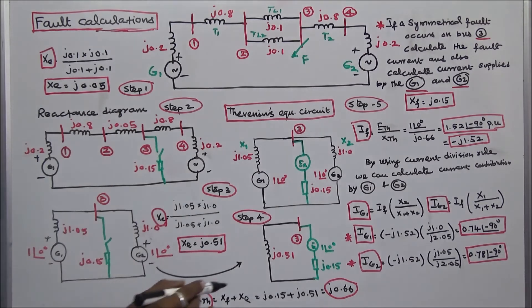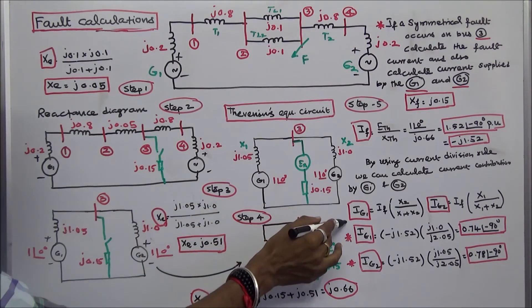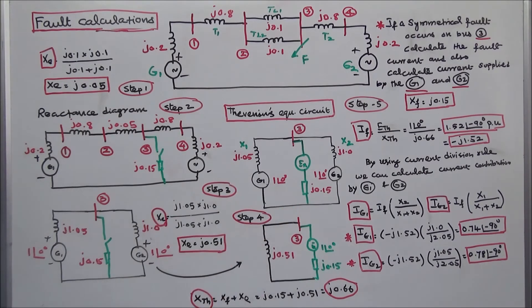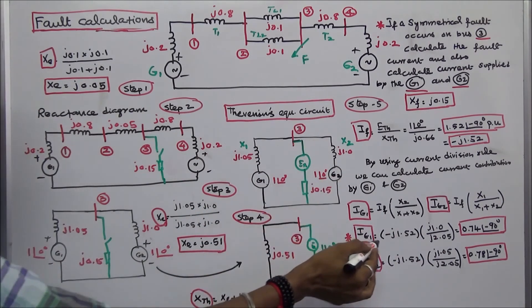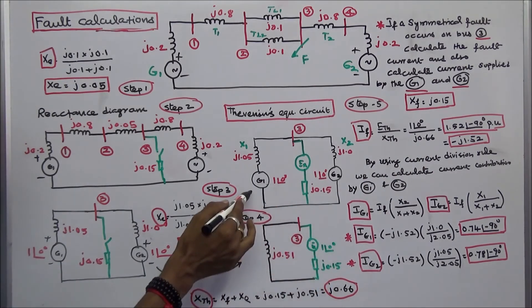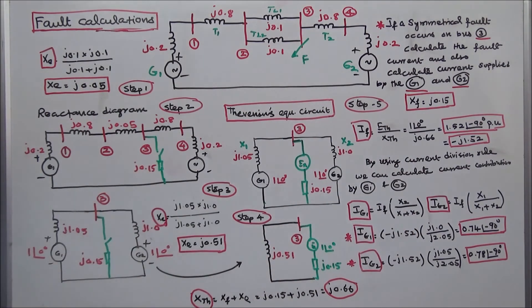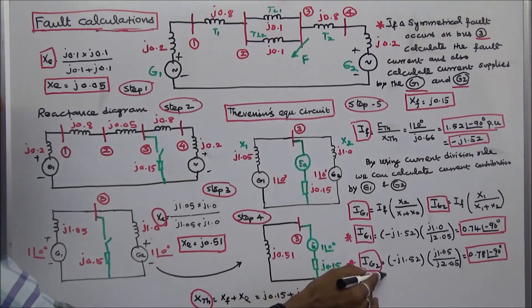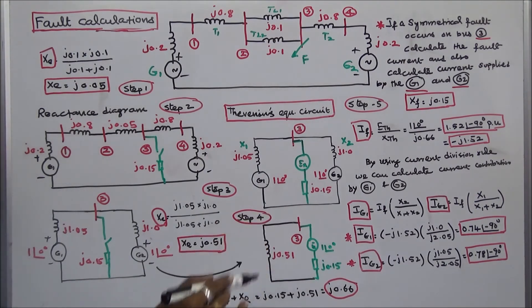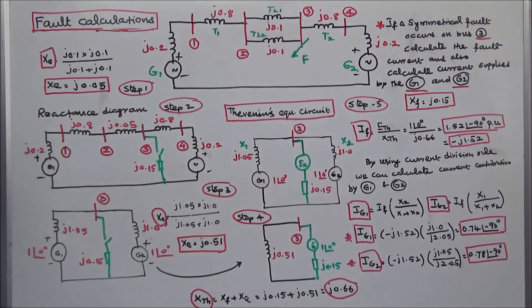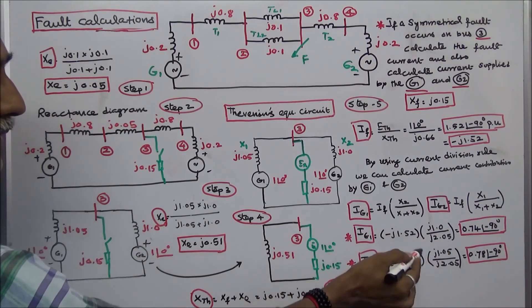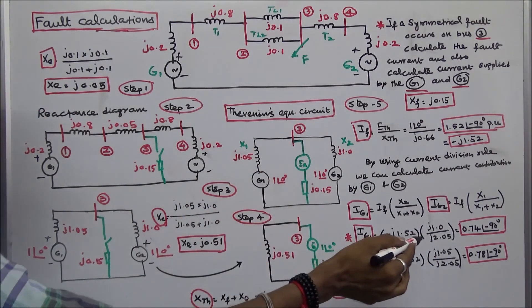The second part requires calculating the current supplied by generators G1 and G2 using the current division rule. IG1 equals the fault current multiplied by X2 divided by X1 plus X2, where X2 equals J1.0 and X1 plus X2 equals J2.05. With fault current minus J1.52, the current supplied by generator 1 is 0.74 angle minus 90 degrees. Similarly, IG2 equals minus J1.52 multiplied by J1.05 divided by J2.05, giving a current supplied by generator 2 of 0.78 angle minus 90 degrees.